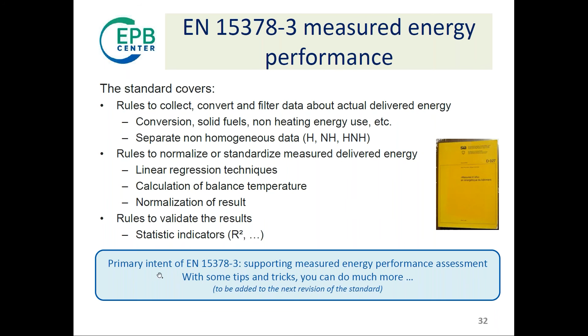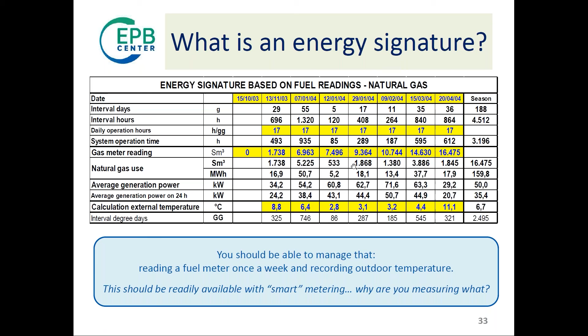Is that difficult? One of the methods is the energy signature. You see here a simple Excel sheet where, in yellow, you have the data you input: the date when you read the meter, how long the system worked during the day, the gas meter reading, and the only difficult data, the external temperature during the measurement interval. All the rest is just the energy consumed and the power, by dividing energy consumed by the duration of the interval. The result, if you present the data, is this curve.